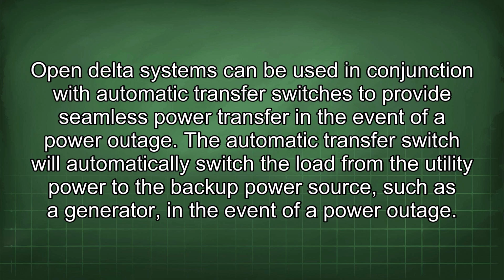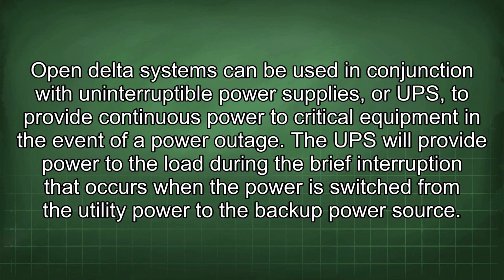The automatic transfer switch will automatically switch the load from the utility power to the backup power source, such as a generator, in the event of a power outage. Open Delta systems can be used in conjunction with uninterruptible power supplies, or UPS, to provide continuous power to critical equipment in the event of a power outage. The UPS will provide power to the load during the brief interruption that occurs when the power is switched from the utility power to the backup power source.